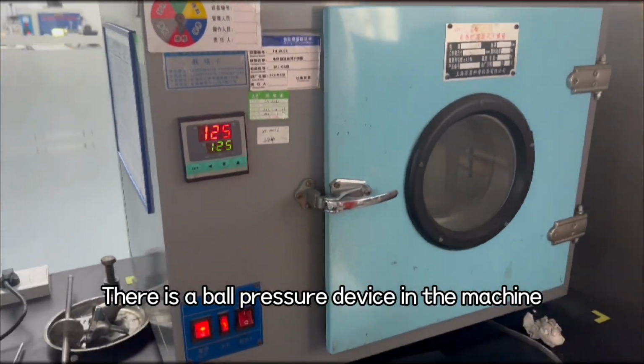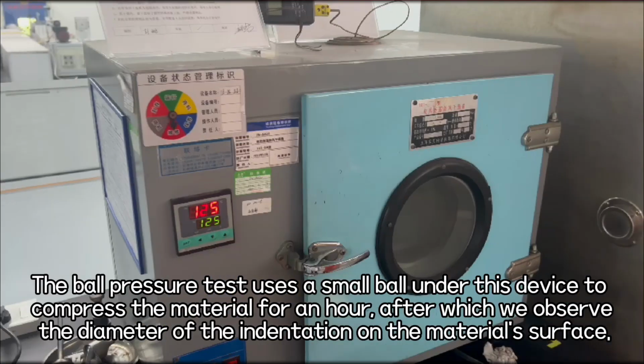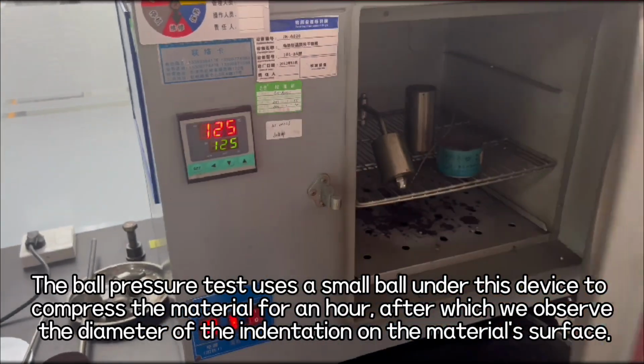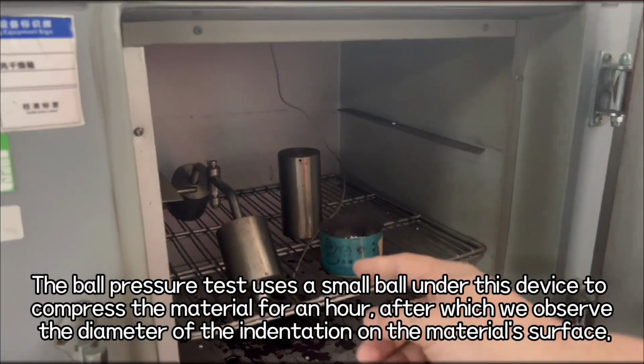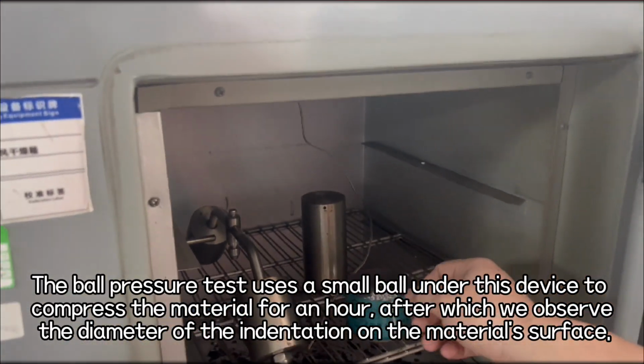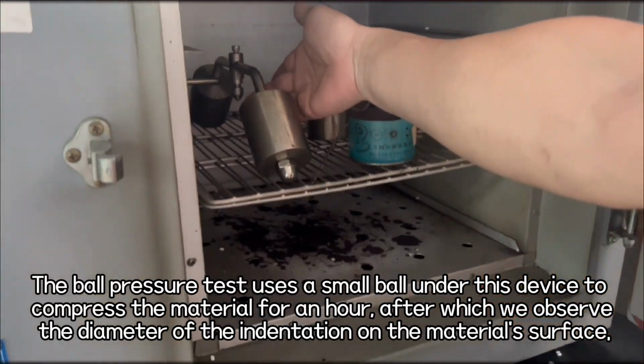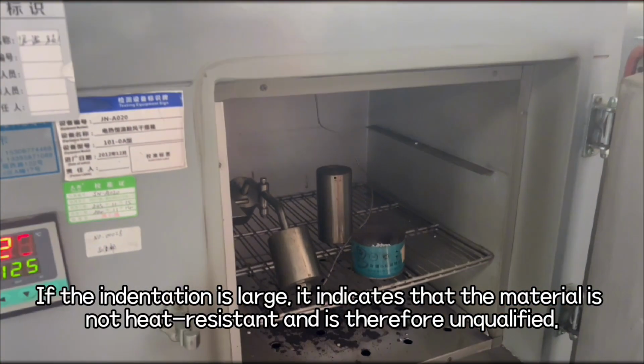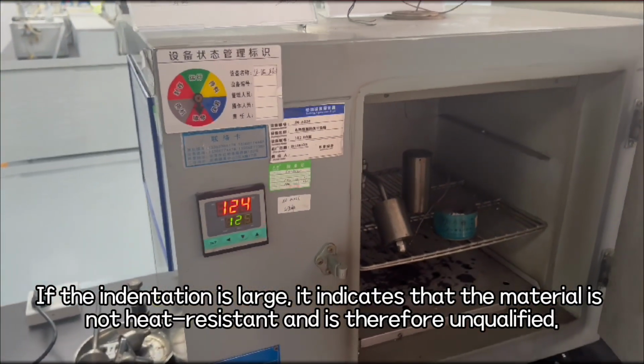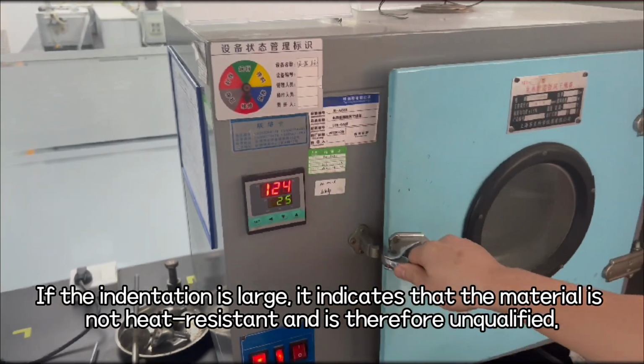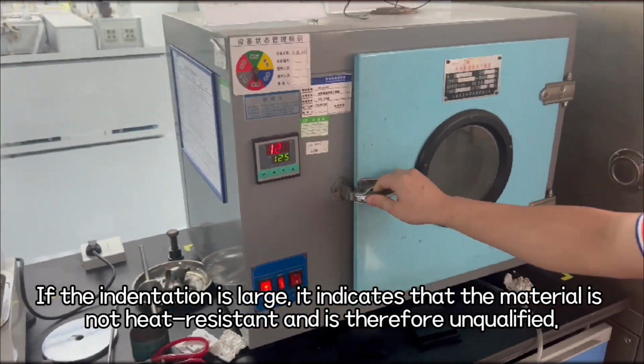There is a ball pressure device in the machine. The ball pressure test uses a small ball under this device to compress the material for an hour, after which we observe the diameter of the indentation on the material's surface. If the indentation is large, it indicates that the material is not heat resistant and is therefore unqualified.